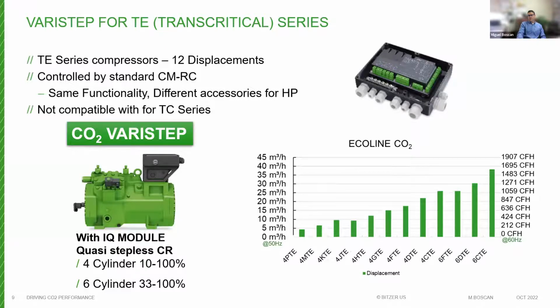So this means that technicians and users will not need to learn new software or connect with new hardware with the CO2 compressors. There are some accessory differences that connect to the CO2 compressor, like the pressure transducers and temperature sensors. They are rated for higher pressure, but the hardware module and the software are the same.